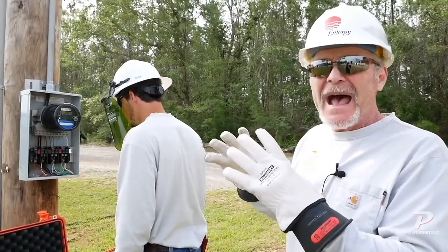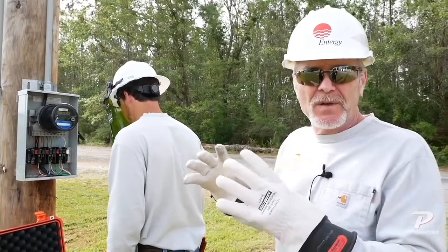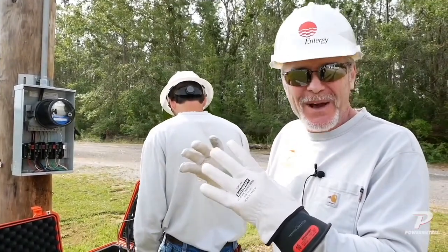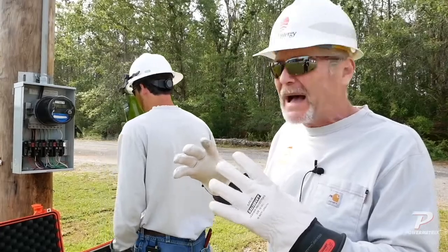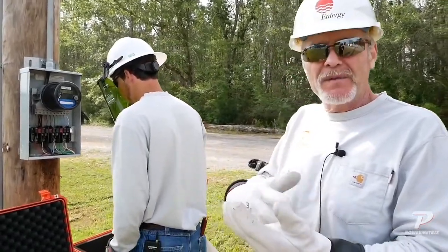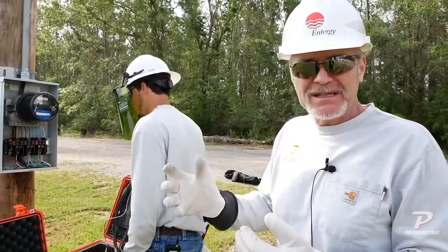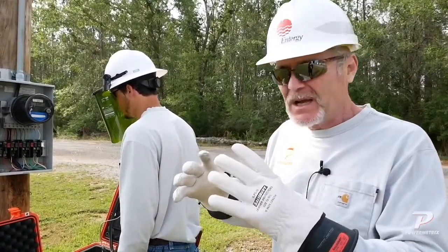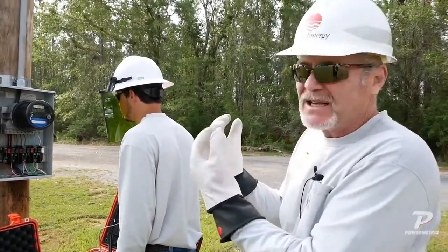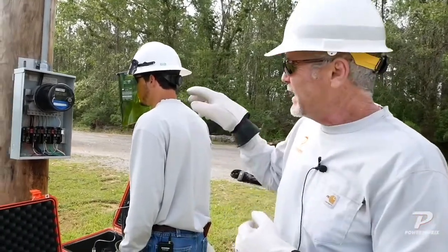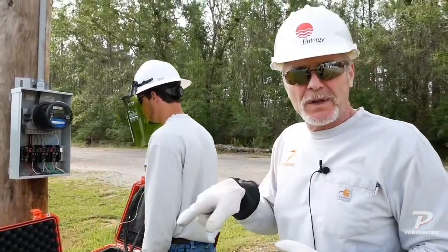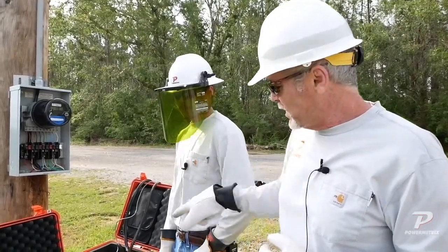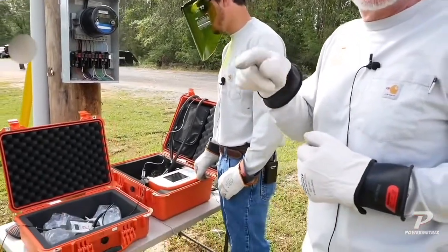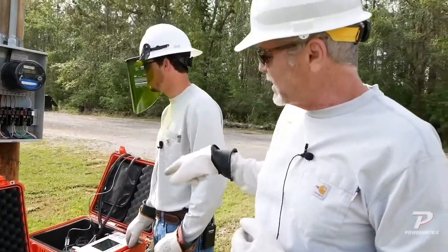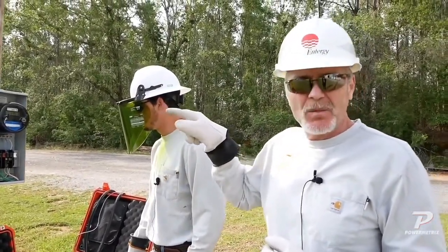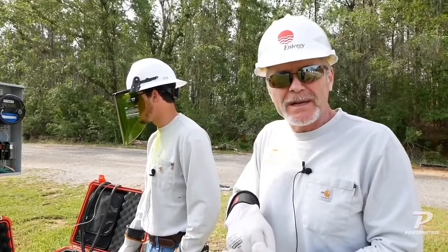So it tells you what's actually going on at the customer, which you can hear the noise behind you and know that we do have a customer right here going. So it's telling you what's going on behind that wall, right? Because it's taking all of the connections and everything into account and the CTs, whereas a phantom load test is where you pull that meter or you disconnect it from those CTs and all that wiring, and you just test just that meter. You run it off of a load box here in the field. You can use a load box like we have here and run that phantom load test, or you can use a customer load test like we're going to do now and use the CTs and what's the actual load of the customer, what's going on today.